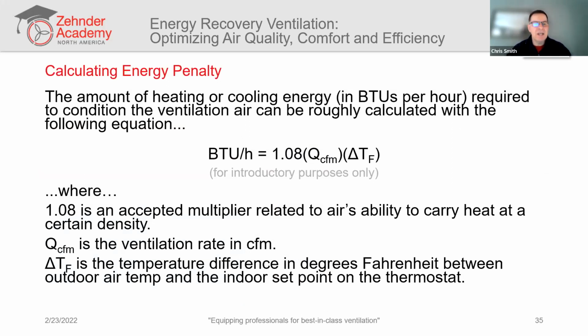A simple way of estimating that energy penalty is by using this calculation. You can arrive at your BTUs per hour, your energy penalty, by multiplying a basic multiplier times the ventilation rate in CFM times the difference in temperature. In this case, we'll use 1.08 as the multiplier. This is basically relating to air's ability to carry heat at a certain density. We'll use CFM as our ventilation rate, and the difference in temperature, in Fahrenheit, is the difference between outdoor air and indoor air. And we can arrive at our BTUs per hour.